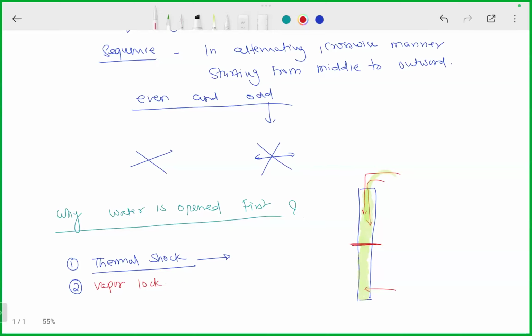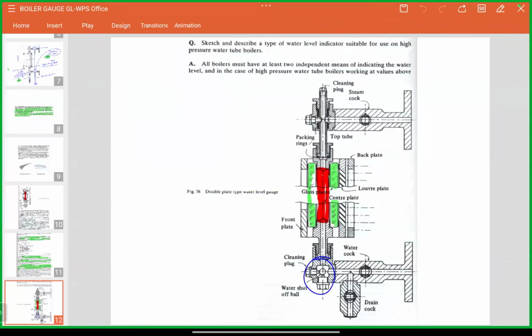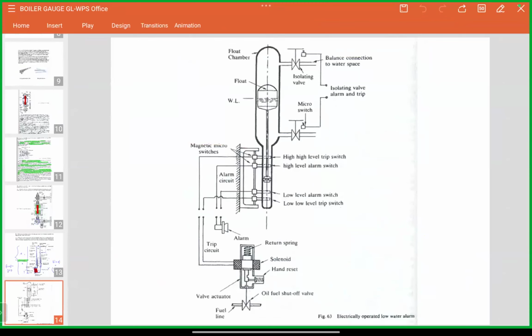In your boiler, in addition to gauge glasses, there has to be some other electrically operated water column fitted with either a float ball or multiple magnetic micro switches, which is useful in determining the level as well as giving an alarm.